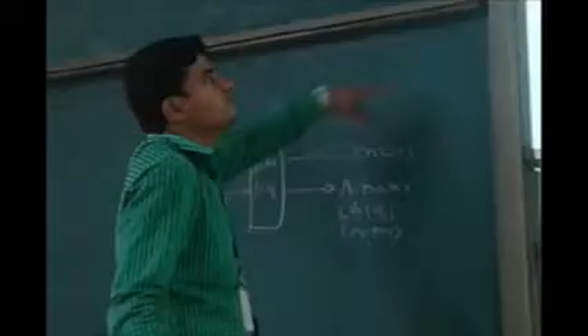Next one is the alarm feature. The alarm feature is to set certain parameters for the alarming conditions. For example, my requirement for temperature is 200 degrees. If I set the base at 200, I will set limits of 10 degrees on either side, so 190 and 210. If my temperature goes beyond 210 degrees, I give that condition for my alarm users. If the temperature goes below 190 degrees, same thing, I will give that condition in my alarm users.